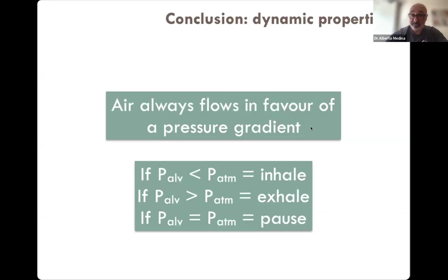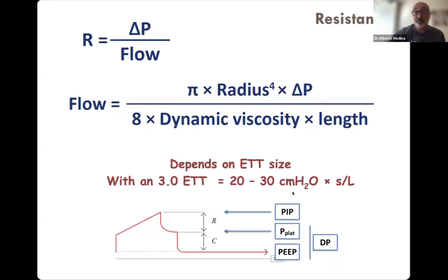The summary of these dynamic properties of the respiratory system is the resistance. This is another constant. If we go down to the graph, the pressure time curve in a volume control mode, as I previously mentioned, the difference between the peak pressure and the plateau pressure is the surrogate of the resistance. This resistance depends most of the time on the endotracheal tube size, and in a small infant with a 3.0 endotracheal tube, this resistance is very high. It depends on the radius of this endotracheal tube.